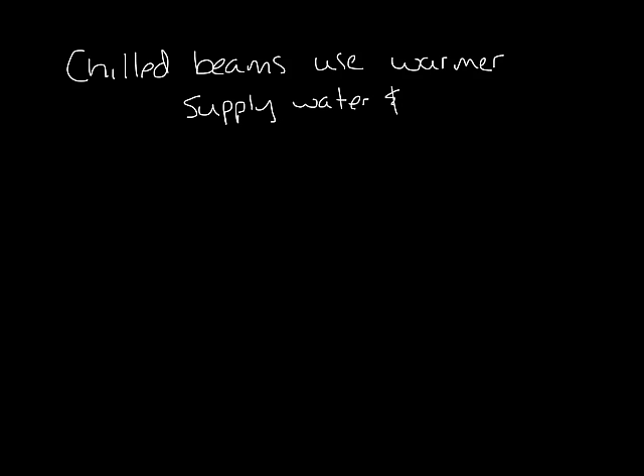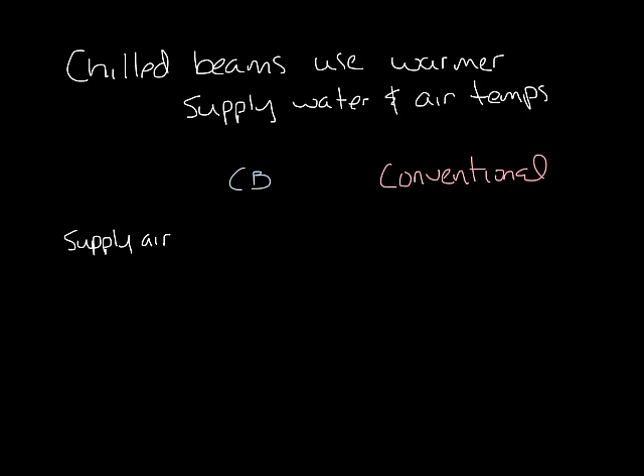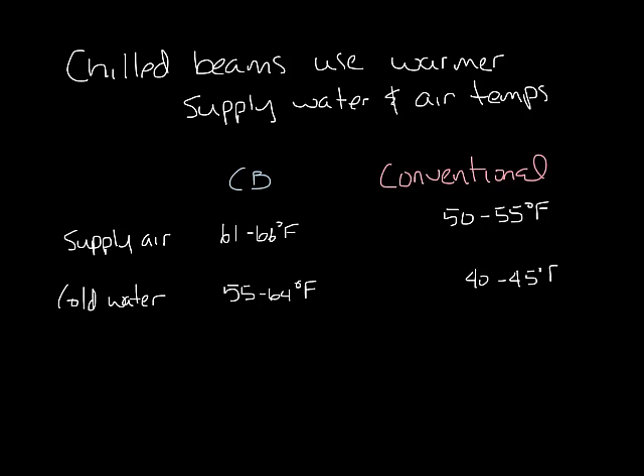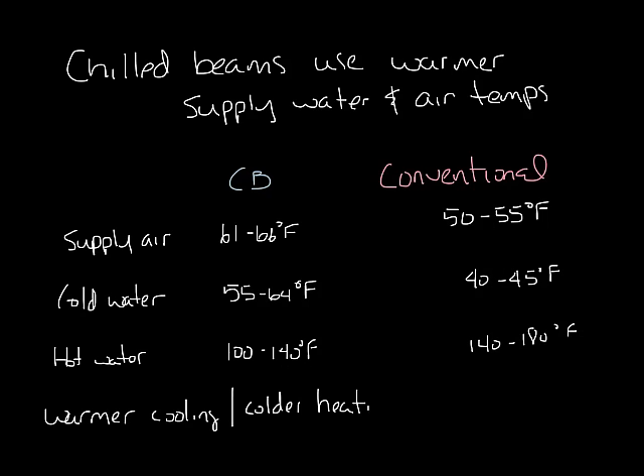Another benefit of chilled beam systems is that they use warmer supply water temperatures and warmer supply air temperatures than a conventional overhead air distribution system. For instance, the supply air temperature of a chilled beam system would be between 61 to 66 degrees Fahrenheit compared to 50 to 55 degrees in a conventional system. The cold water temperature would be 55 to 64 degrees for a chilled beam compared to 40 to 45 degrees in a conventional system. And the hot water temperatures are 100 to 140 degrees compared to 140 to 180 degrees for a conventional system. This warmer cooling temperature and colder heating temperatures will reduce the energy usage of the building.